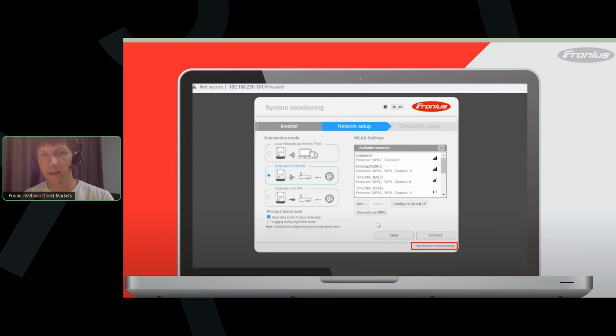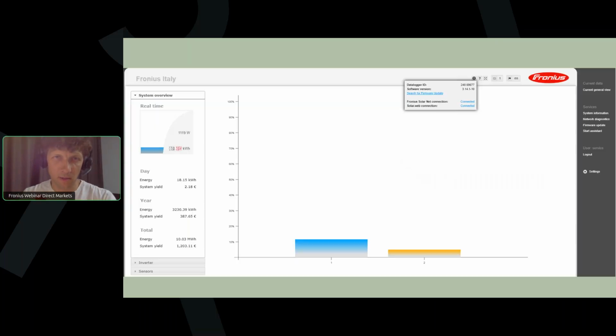The installer sees that the inverter looks like it's working, but because the wizard isn't finished, commissioning isn't finished, and data from the inverter isn't moving to our cloud and monitoring. So monitoring isn't working, and usually the installer has to come back to the site and finish commissioning. So be sure that you completed commissioning, and everything will be okay.